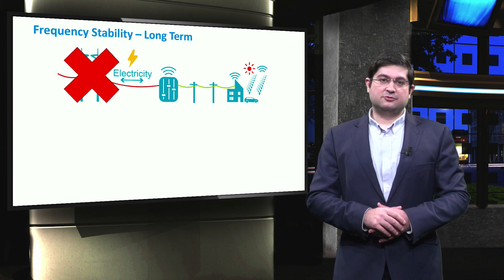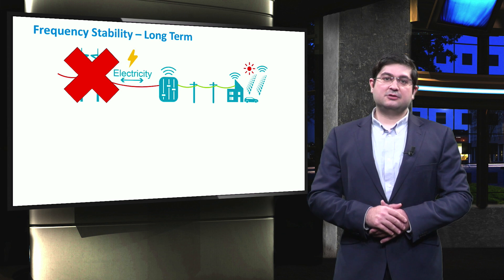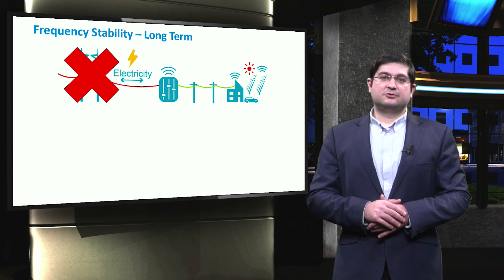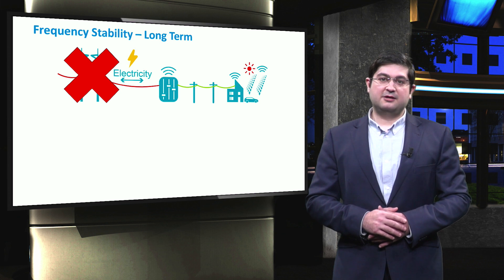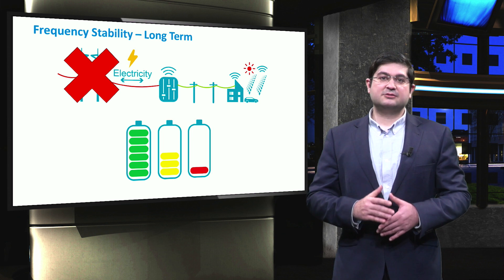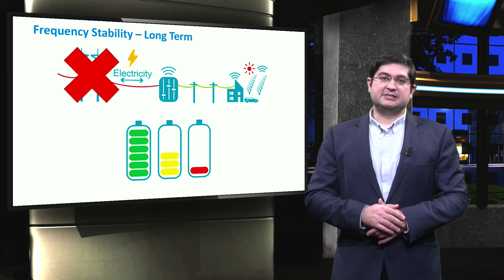After primary frequency control, the secondary frequency control will be activated, which is also known as the load frequency control. The secondary control is the main responsible to recover the frequency to the nominal value. In islanded microgrids, various components could support secondary frequency control, such as batteries.